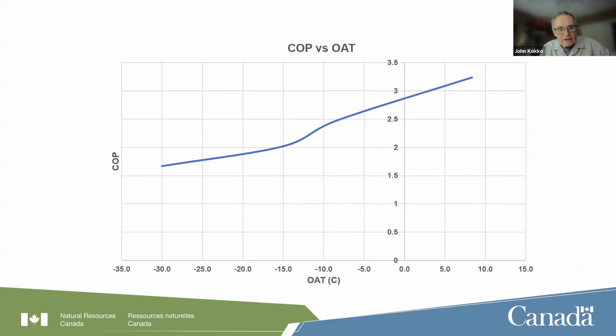The next part of the equation is that the coefficient of performance, or the efficiency of the heat pump, also drops as the outdoor air temperature gets colder. So while the manufacturer may say we've got a COP of 3.5 or something, that's usually at a very high temperature. So if we're looking at what heat pump we're going to put in, we've got to be careful to recognize that not only does the capacity go down, but also the energy efficiency of the heat pump goes down.